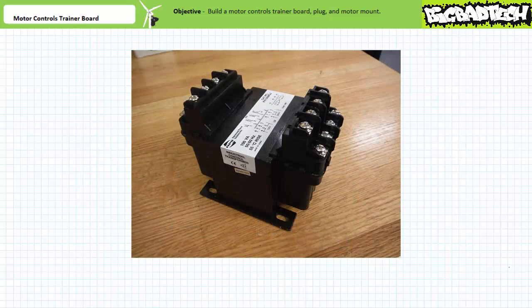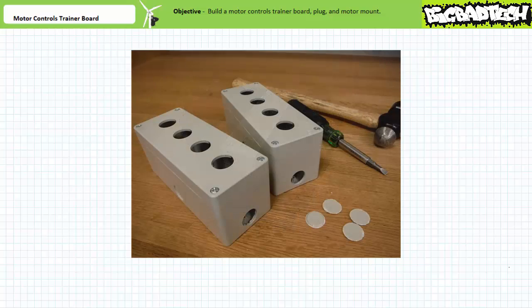Finally, you need to make a choice up front about which level of pilot voltage you'll be using for your motor controls projects. Either 120 volts AC provided by a control transformer, or 24 volt DC provided by a power supply. In this case, we're going to go with a 120 volt AC control transformer directly mounted to the metal plate. First, pop out the knockouts in the top and bottom of each push button enclosure and set them aside for now.